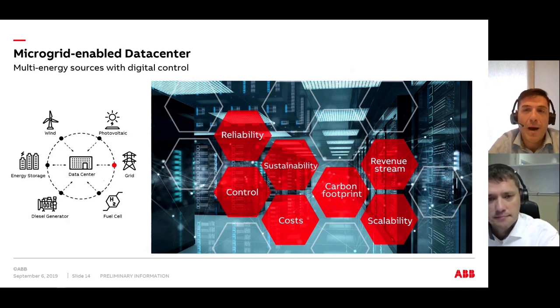But the control system of the microgrid is going to be responsible for isolating from the grid and resynchronizing with it, going from one condition to another. So the battery energy storage, when islanded, is going to prevent those large frequency deviations under the islanding conditions. And it can as well perform a full black start if it's needed.